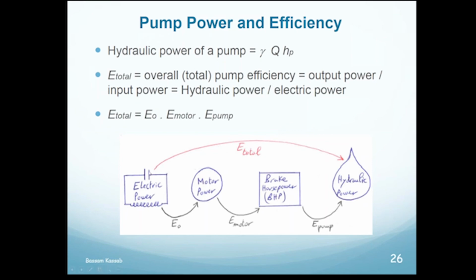So I plotted that diagram in this way. The input power is the electric power, causing the pump to run, and the overall efficiency gets you to the hydraulic power. The hydraulic power has to be less than the electric power because you lose power in the system. The total efficiency is the output power over the input power, which is the hydraulic power over the electric power. This is the multiplication of the smaller efficiencies here.